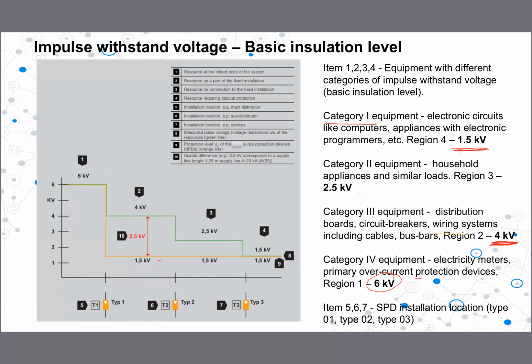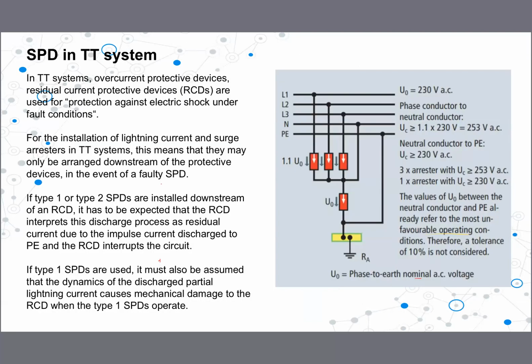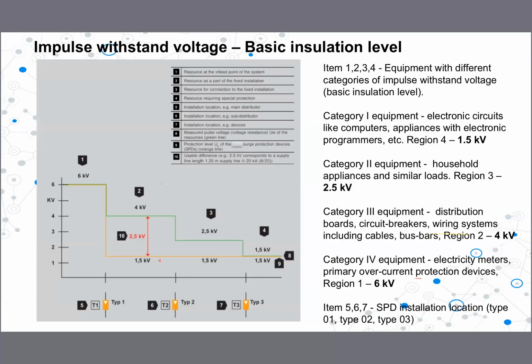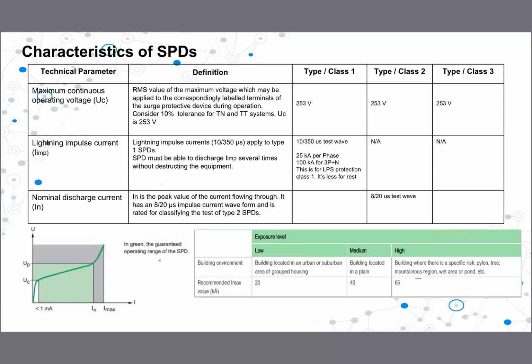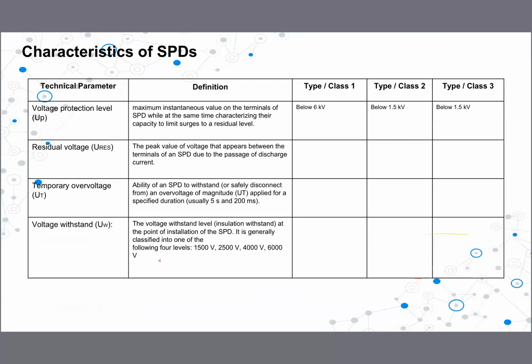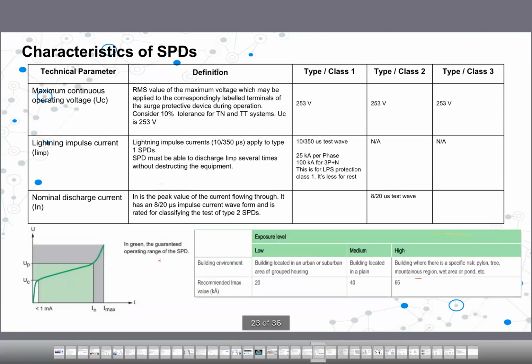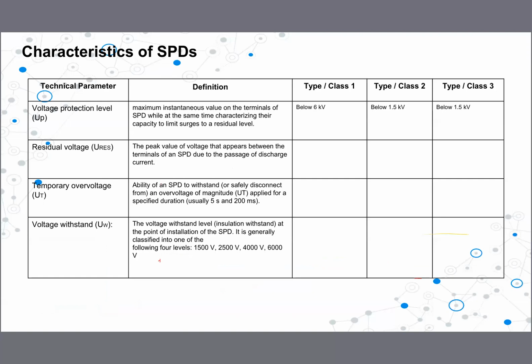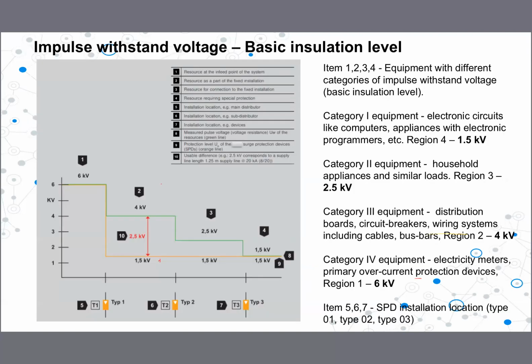So then let's look at how we install. Now you know what the technical parameters are, right? These are the important technical parameters: maximum continuous operating voltage, lightning impulse current, nominal discharge current, right? Then voltage protection level, UP is this one, right? So that's what we discussed just before, right? Then residual voltage level, temporary voltage, then voltage withstanding. These parameters are given with the surge protection device. So we need to do a proper evaluation of these parameters before we select the device, right?